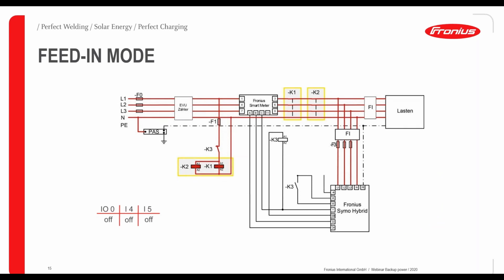Basically in the feed-in mode, so normal grid supply, K1 and K2 are closed because they get power supply. They are supplied via L1, F1 and K3. Here these two contactors are supplied and switch on, and so you get the grid power to our loads and to the Fronius Symo Hybrid inverter. In this moment the inverter will run and there's no feedback on I4 and I5, so they're all off. That means for the inverter, okay, this is feed-in mode.